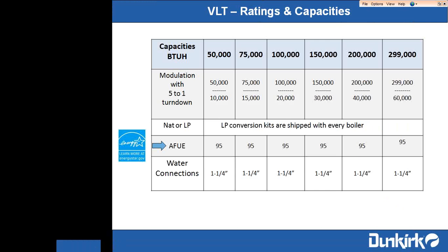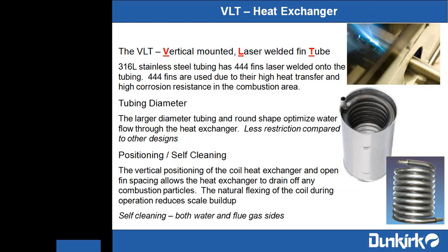Okay, so we make the boiler in 6 sizes from 50 through 299,000 BTUs. And each model modulates with a 5-to-1 turn-down ratio. Some other nice features is that there's an LP conversion kit standard with every boiler. They're shipped natural gas from the factory, and it's simply a brass orifice to change it from natural to propane. After the DOE retesting and re-regulation of condensing boilers, we maintained a high efficiency. We're 95% AFUE on all sizes.